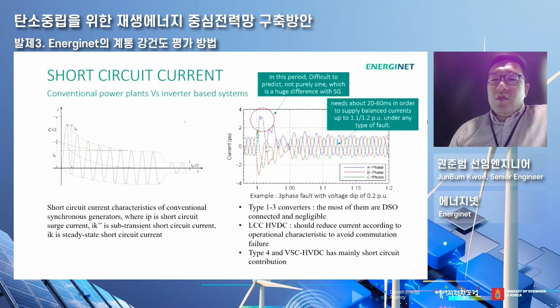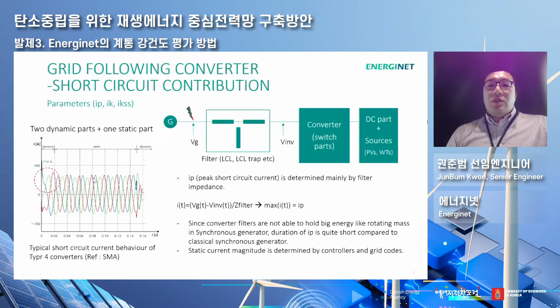Let me elaborate. Now, this is the grid-following converter short circuit contribution. You can see here that since converter filters are not able to hold big energy like the rotating mass in a synchronous generator, the duration of IP is quite short compared to a classical synchronous generator, and the static current magnitude is determined by the controller and grid codes. You can see on the left the typical short circuit current behavior of type 4 converters. It can come back to the normal stage quickly. So the dynamic area is very short, and the static we can easily reach. And here, the static area is 1.2 pu. Yes, that's the method that we use.